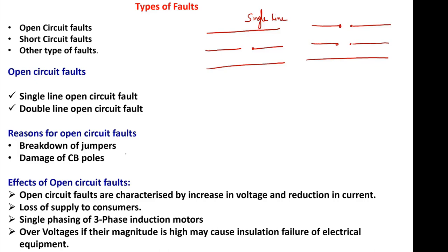What are the effects of open circuit faults? Open circuit faults are characterized by increase in voltage and reduction in current. When an open circuit occurs, in the remaining phases the voltage will increase and the current will reduce. Another effect is loss of supply to consumers connected to the disconnected phase. Three-phase induction motors operating on two phases experience single phasing, which will damage the motor.